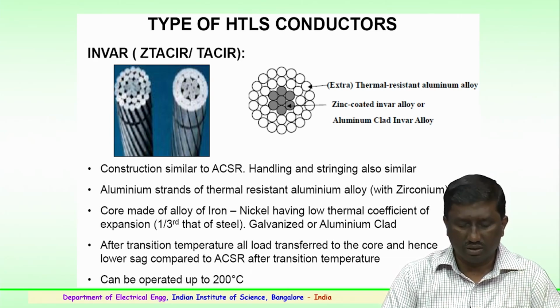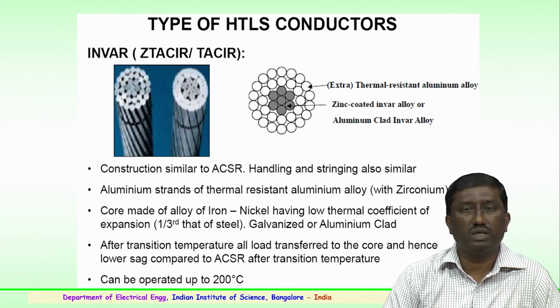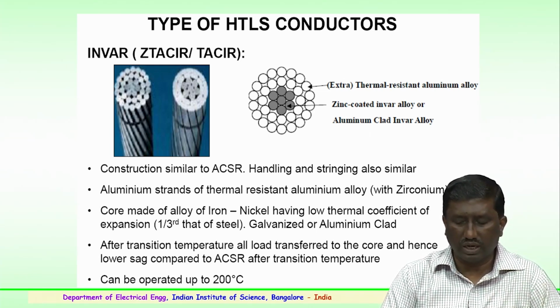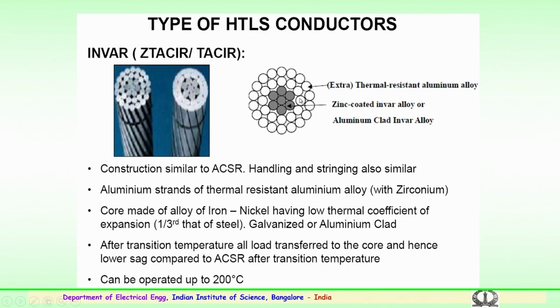The core is galvanized or aluminum clad. So, after the transition temperature, the entire load is transferred to the core of the conductor, and hence the sag is low compared to that of an aluminum conductor steel reinforced after this transition temperature. So, this is an important aspect. After the transition, the entire load is transferred to the core, which consists of aluminum clad invar alloy or zinc coated invar alloy. This helps the transition temperature, when compared to the ACSR, get reduced. This will help in reducing the sag.